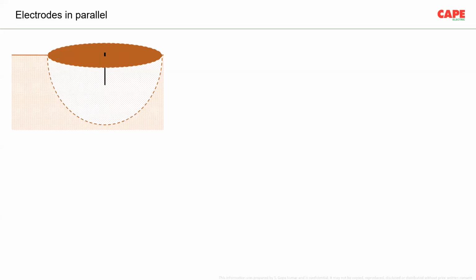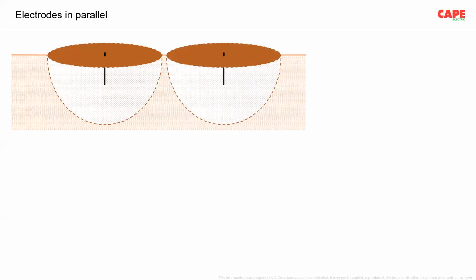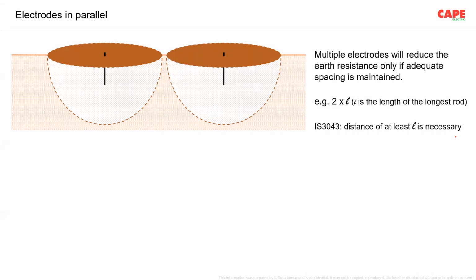Earth electrodes in parallel. In order to reduce the resistance of the earth electrode, a technique which is used is to have multiple earth electrodes in parallel. Remember, each earth electrode has got a sphere of influence. And if the second electrode is away from the sphere of influence of the first one, like the one in the picture, then you get a better value. Earlier days, we were always saying that the distance between two earth electrodes is 2L. Imagine the length of one vertical electrode, L, is 3 meters, then ideally, if the distance is more than 6 meters, you get a better value.